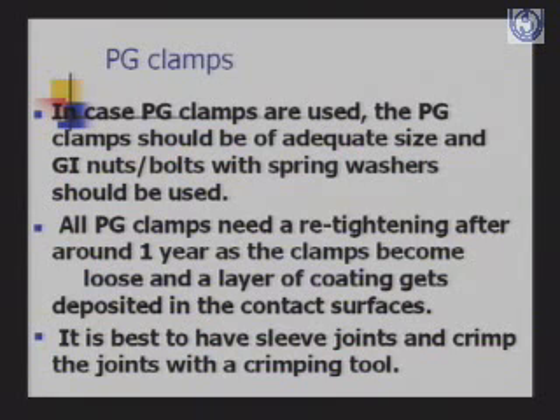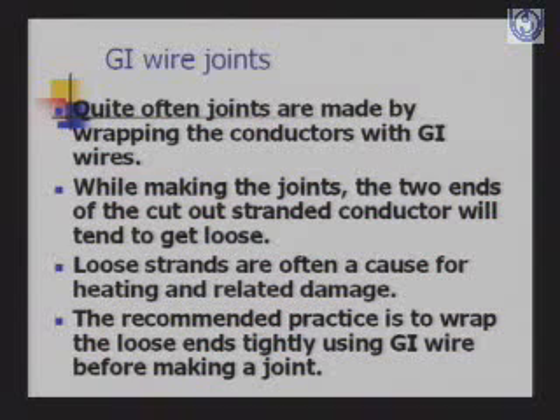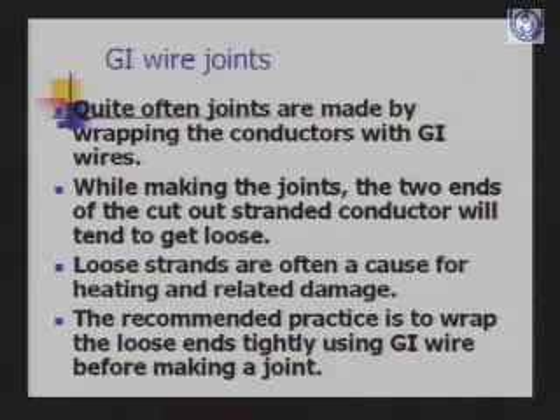It is best to have a sleeve joint and crimp the joints with a crimping tool. Quite often joints are made by wrapping the conductors with GI wires. While making the joints, the two ends of the cutout stranded conductor will tend to get loose. Loose strands are often a cause for heating and related damage. The recommended practice is to wrap the loose ends tightly using GI wire before making a joint.